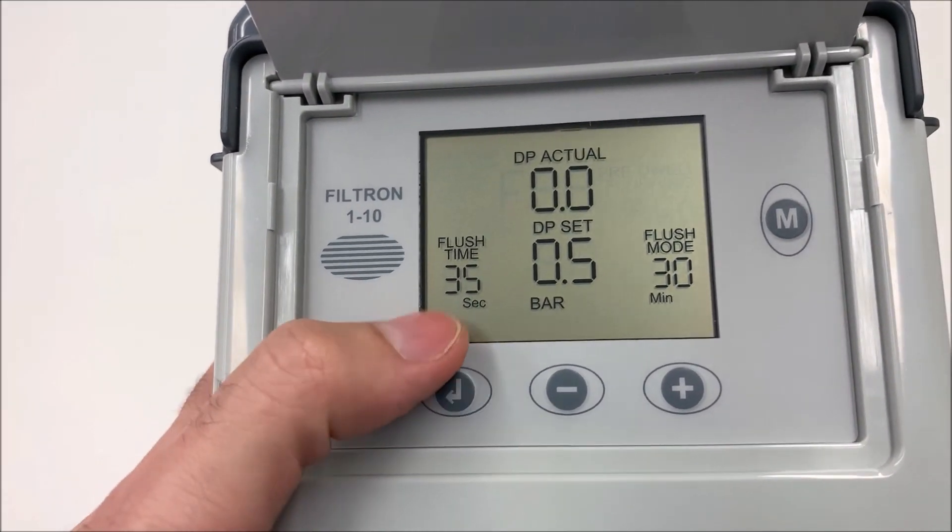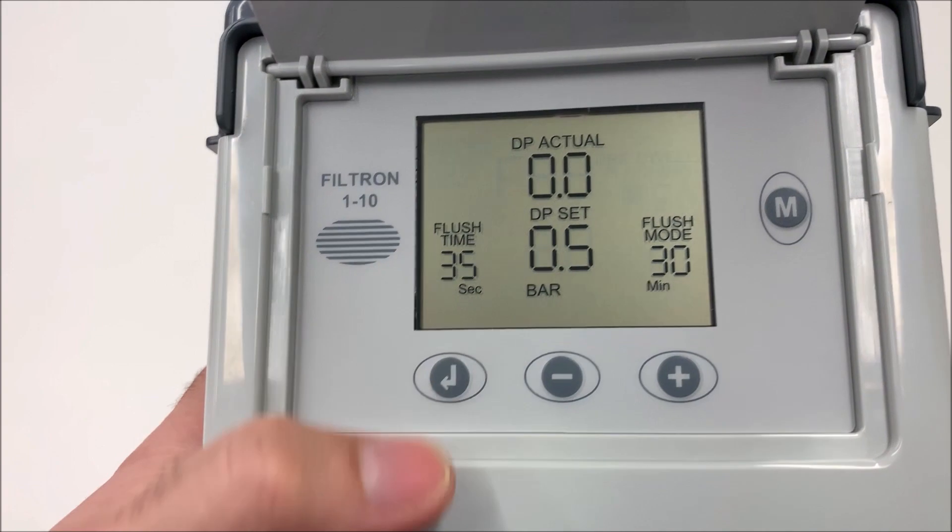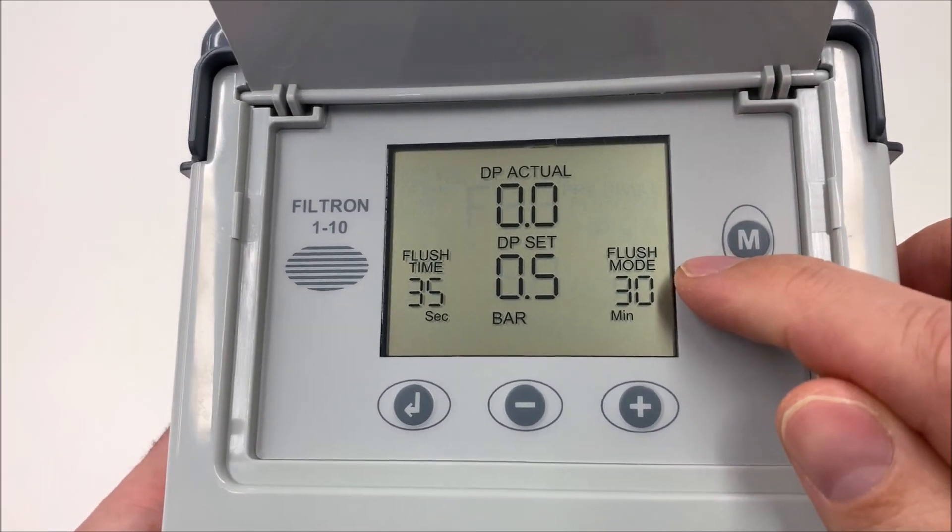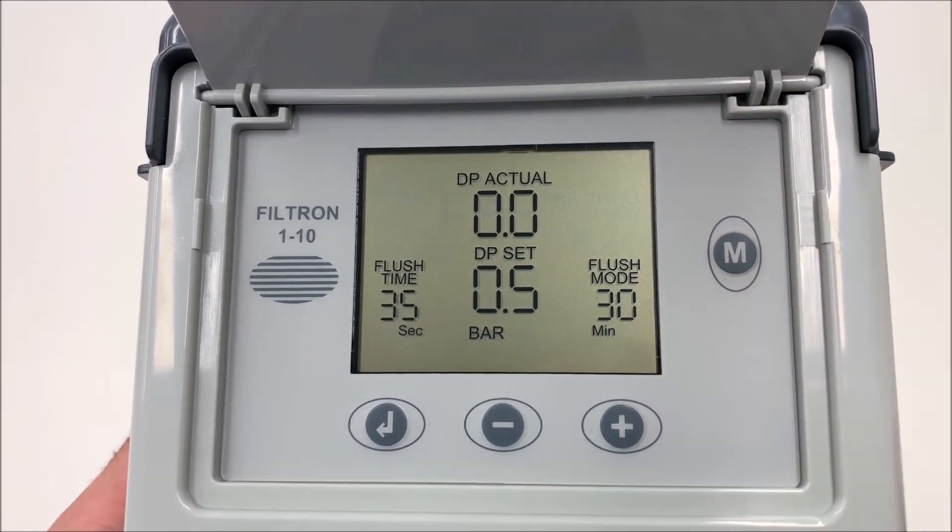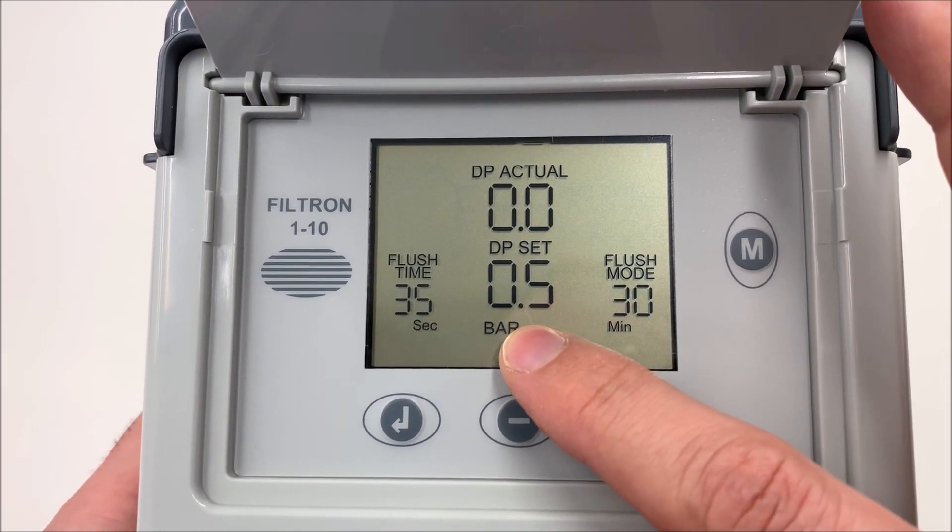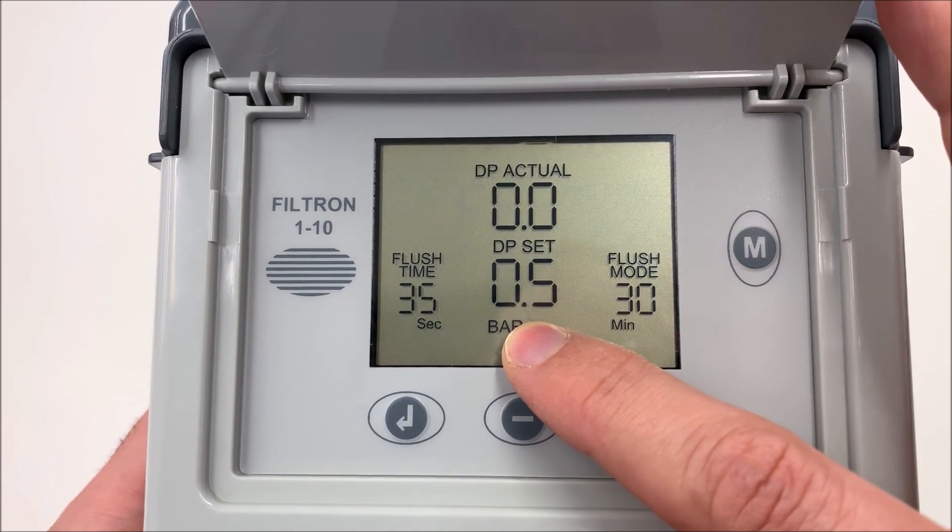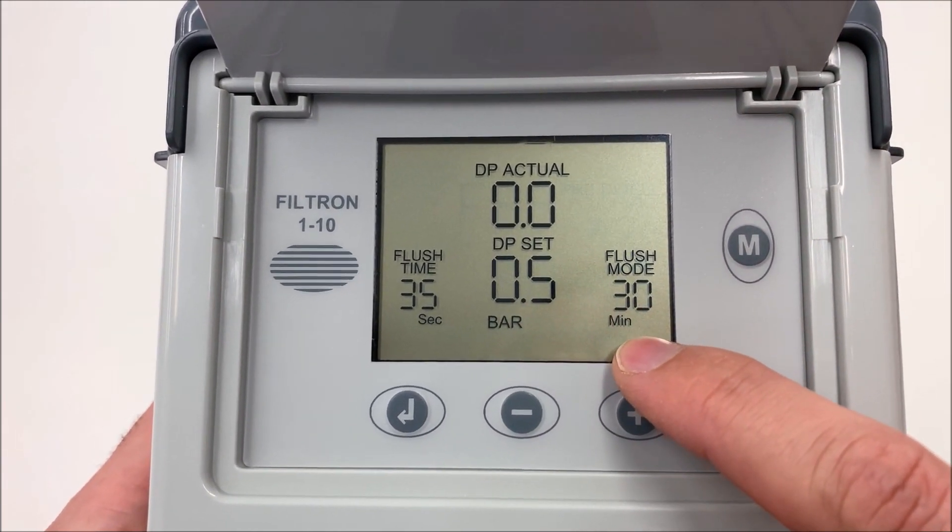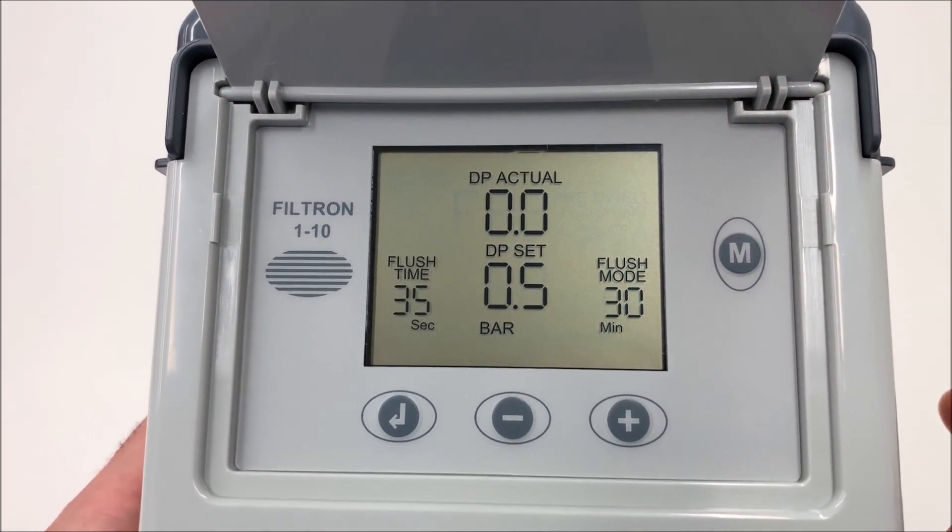Flushing time, in this case, is 35 seconds. And flushing mode is 30 minutes. That means that the thing that happens the first, that we arrive to the preset differential pressure or the preset time, will activate the backwash.